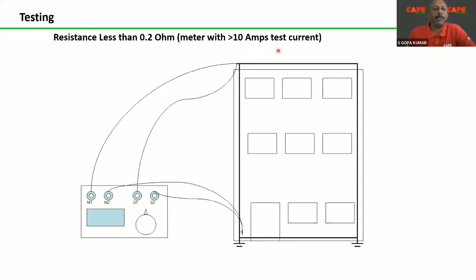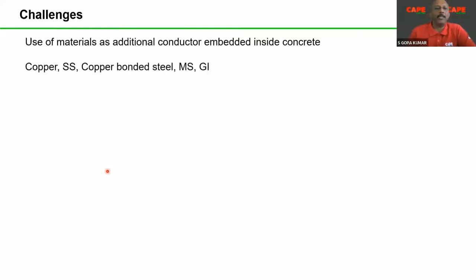Anything higher than 10 amps test current is necessary, and the resistance from the top to the bottom shall be lesser than 0.2 ohms, 200 milliohm. So this is how the performance is ensured. Now, when it comes to embedding or using natural components, we face a lot of challenges.